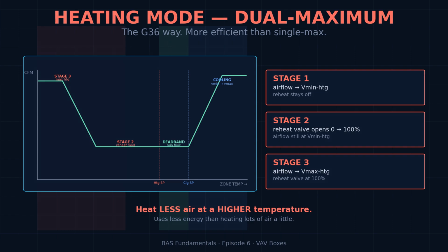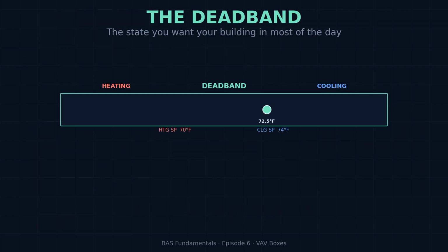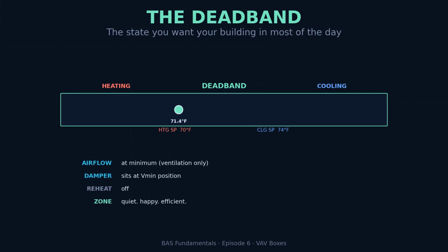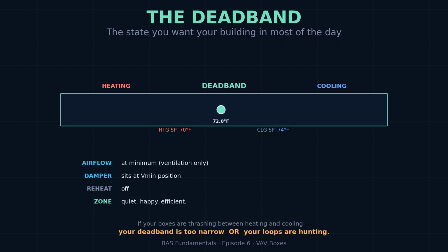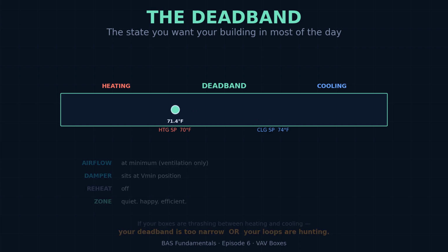You heat less air at a higher temperature, which uses less energy than heating a lot of air a little bit. Between heating and cooling, there's a deadband. Zone temp sits happily between set points. Airflow stays at minimum for ventilation. Reheat stays off. Damper sits quiet. This is the state you want your building in most of the day. If your boxes are thrashing between heating and cooling, your deadband is too narrow or your loops are hunting.